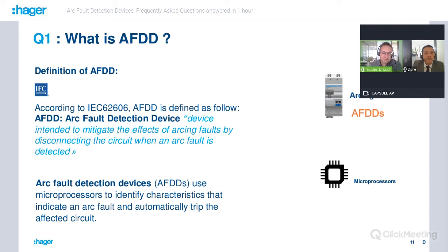Okay, it's a very simple, basic question, but it's very important to have a clear definition of what AFDD is. According to IEC 62606, the product standard, the AFDD is defined as a device intended to mitigate the effects of arcing faults by disconnecting the circuit where an arc fault is detected. AFDD, arc fault detection device. The AFDD uses microprocessors to identify characteristics that indicate an arc fault and automatically trips the affected circuit. So there is the specific point of this AFDD, with a high focus on the microprocessor and automation.